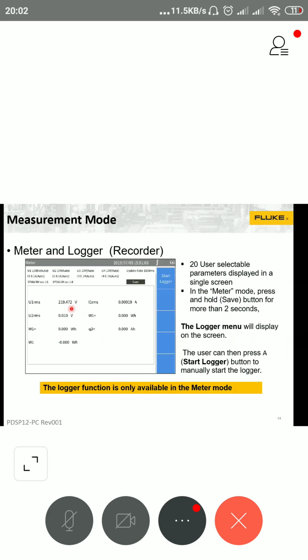And the important part of this equipment is the meter. Generally, in the display of any power analyzer, you can see selected readings up to 5 to 6 parameters, and if you want to read more parameters, you have to scroll down. Here Fluke has thought about that, and they have allowed the end user to choose up to 20 parameters in a single screen. In a single screen, you can see up to 20 parameters in one shot, and you can verify.